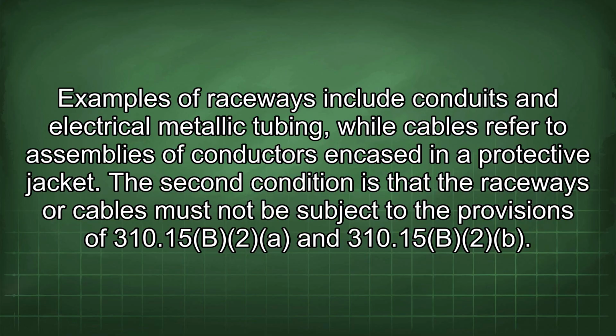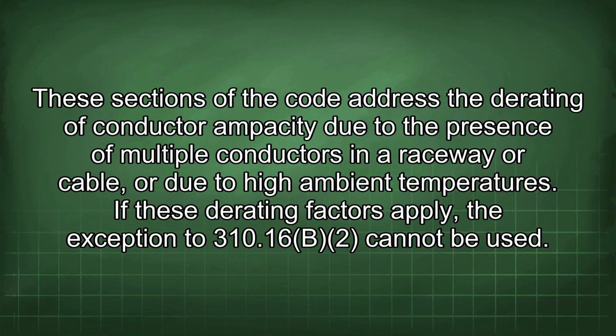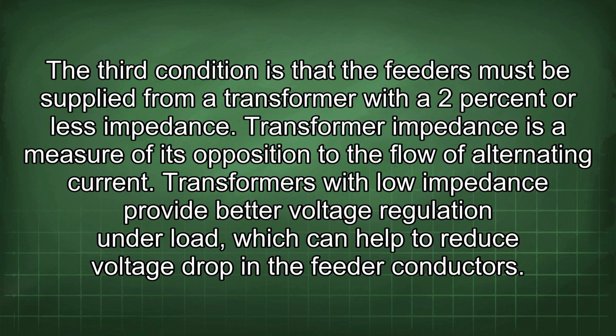The second condition is that the raceways or cables must not be subject to the provisions of 310.15(B)(2)(a) and 310.15(B)(2)(b). These sections of the code address the derating of conductor ampacity due to the presence of multiple conductors in a raceway or cable, or due to high ambient temperatures. If these derating factors apply, the exception to 310.16b2 cannot be used.